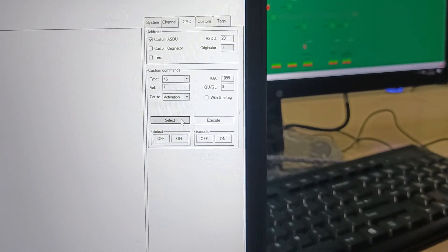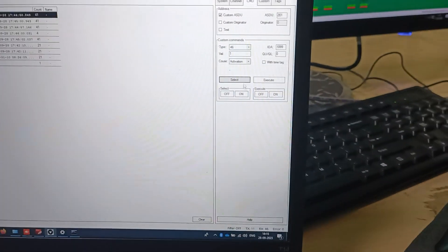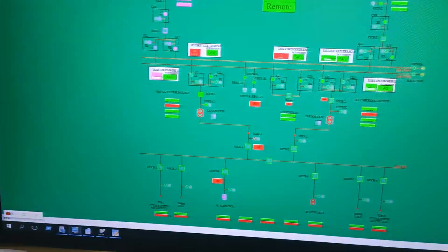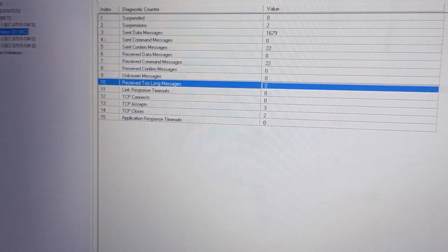Select. But before, you can see in the middle — Q05, 132 KV — I have a CB Close. Now I have a command. This is my master, that is the gateway, this is the SLD. So I have a command, I have a breaker. Execute — Select, On, Execute. And I have a sound. At the same time you can see it receive. Bay 5 — I have a Close, then Open.